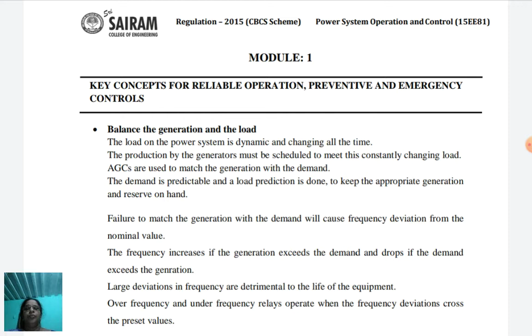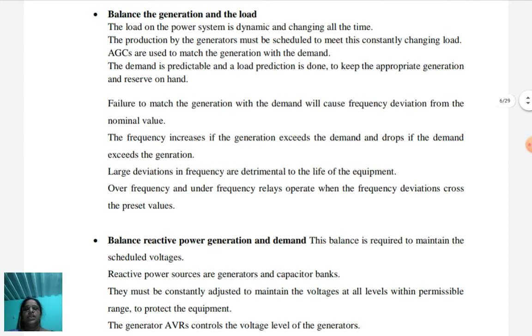The failure to match the generation with the demand will cause frequency deviation from the nominal value. The frequency increases if the generation exceeds the demand and drops if the demand exceeds the generation. Large deviations in the frequency are detrimental to the life of the equipment. Therefore, the over frequency and under frequency relays operate when the frequency deviation crosses the preset values. This is the first key point of the reliable operation, preventive and emergency control of power system operation and control.